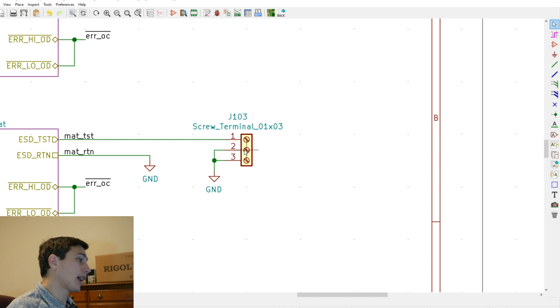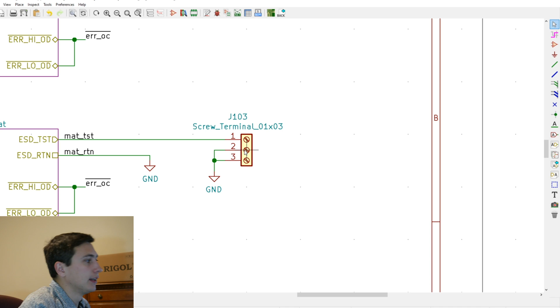The first option is you can ground the mat on the same terminal block, but then you could actually have a broken wire from this design to ground and not detect it. So if the ground wire from earth to this circuit is broken, you wouldn't detect that, because the mat would be floating along with your detector.